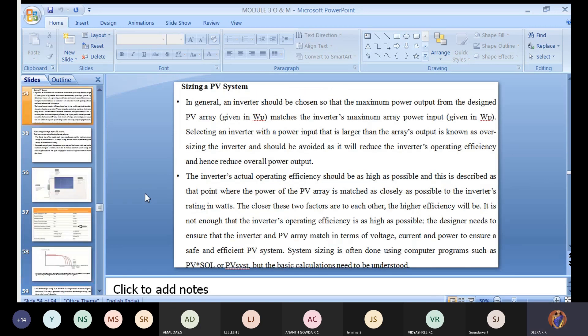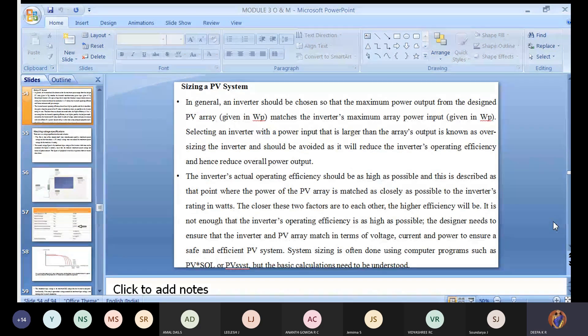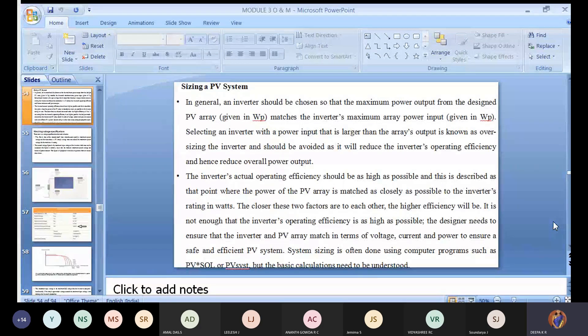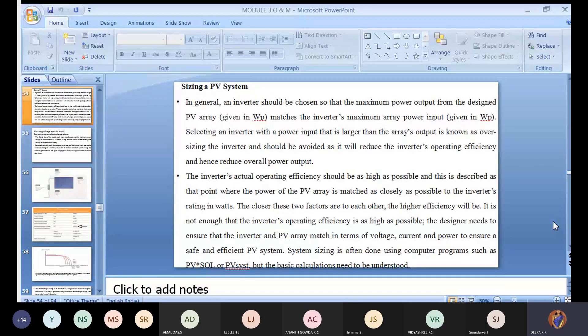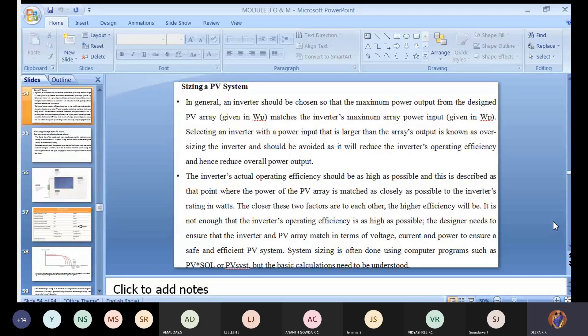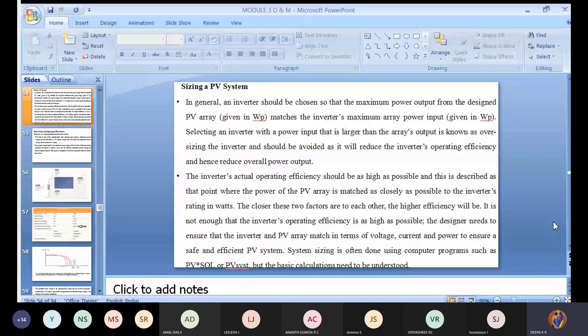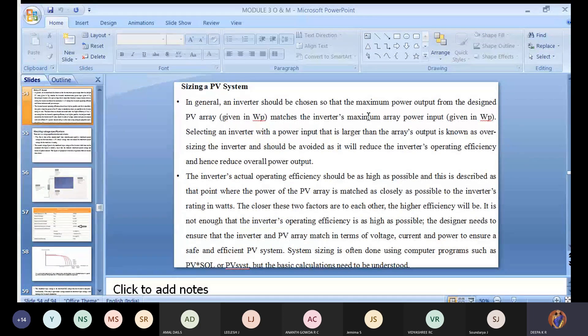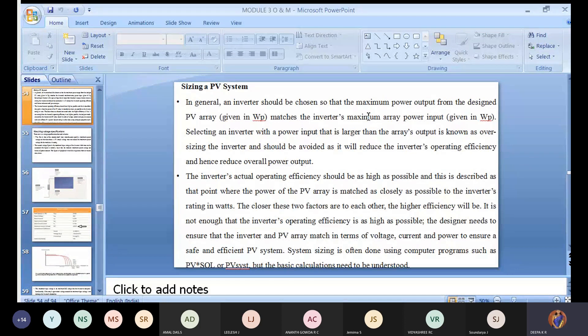Next is sizing of a PV array. Here we're merging all the concepts - talking about inverter, cables, DC cable, AC cable, voltage sizing, current sizing. Everything we're meshing up with this concept called sizing of PV system. In general, an inverter should be chosen so that the maximum power output from the designed PV array matches the inverter maximum array input.